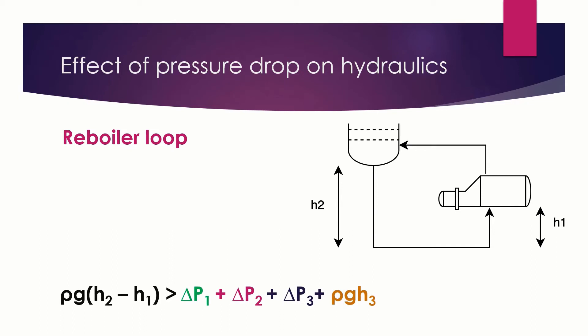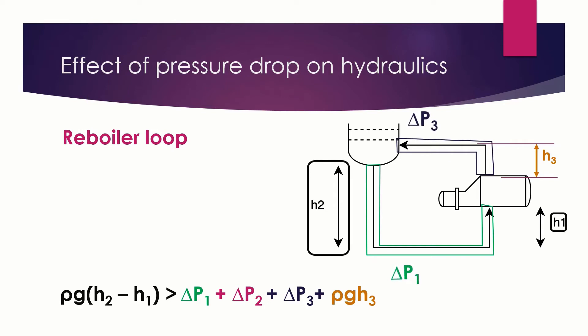The only driving force here is the difference between the liquid density here and the vapor density here. The liquid density is much higher than the vapor density. So this means that this loop is very critical. We will need to increase the difference between H2 and H1 and minimize the pressure drop in the pipes here and the pressure drop in the reboiler.